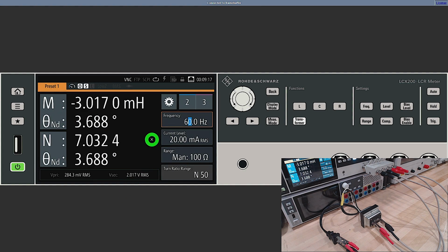So if you go back to 60 hertz over here, now if we have a 6.44, let's say, number of turns ratio, and we have a 120 something volt coming in, we can calculate what the output voltage should be. It should be around 19 volts or so. But is it the case? We can verify by quickly measuring it.